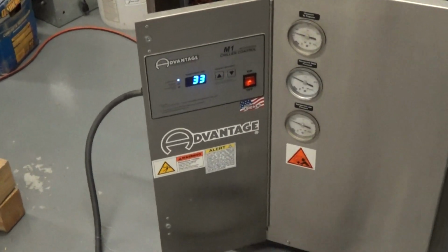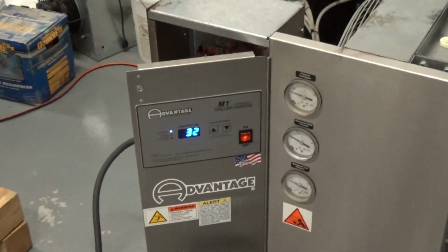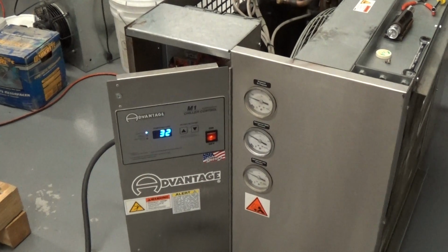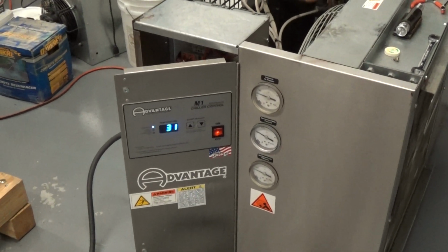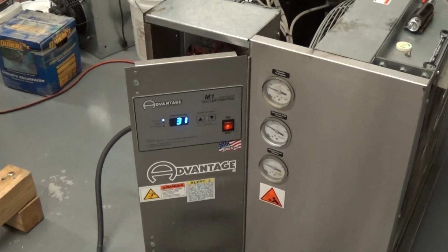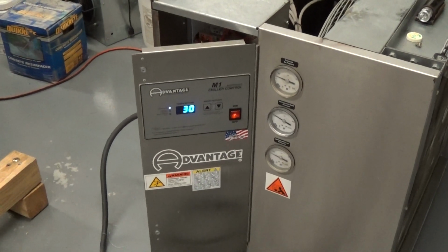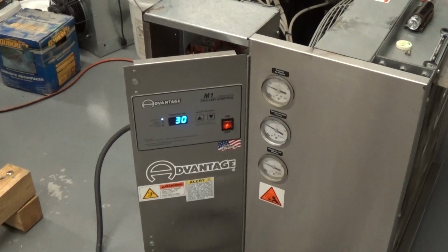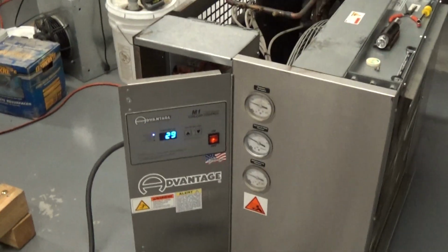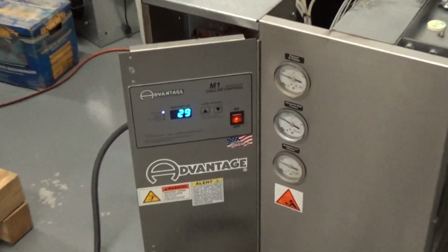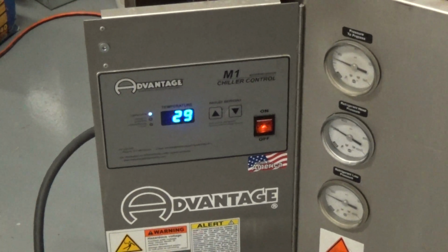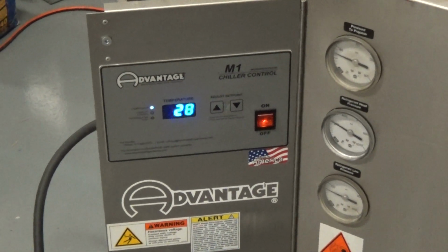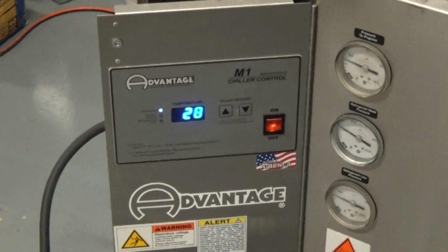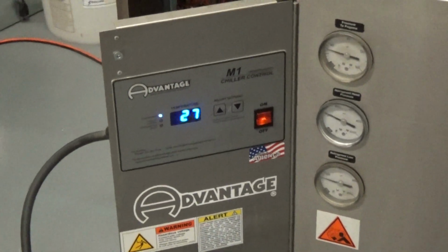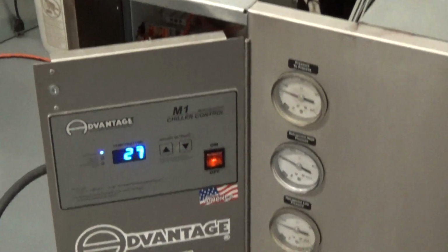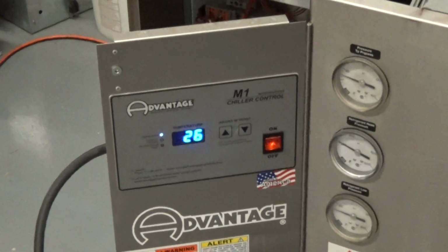If you have a bigger heat load, which we don't, that hot gas bypass or capacity control will allow the compressor to run longer and slow down the speed of the decreasing temperature, like we are in just this room test environment here. As you get down to these colder temperatures with any chiller, with every degree colder you get, the less capacity in BTUs per hour it has. It's like towing a car uphill. So as we get colder, the speed at which that drops decreases, although it's still going down pretty quickly. If you truly need 20, you want to get away with the highest temperature that you can for your process. But if you truly need 20, I'd probably set it at 22 or 23 because it's going to keep chilling until it reaches about 3 degrees below that.